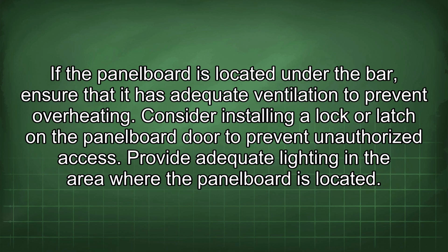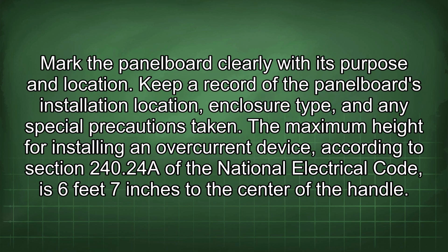Provide adequate lighting in the area where the panelboard is located. Mark the panelboard clearly with its purpose and location. Keep a record of the panelboard's installation location, enclosure type, and any special precautions taken. The maximum height for installing an overcurrent device, according to Section 240.24 of the National Electrical Code, is 6 feet 7 inches to the center of the handle.